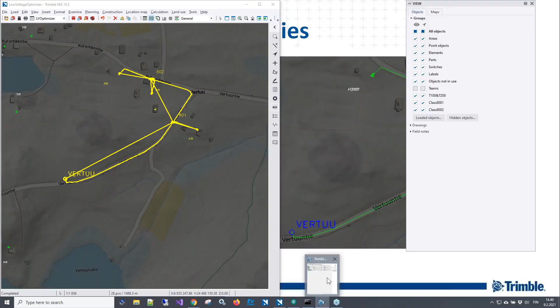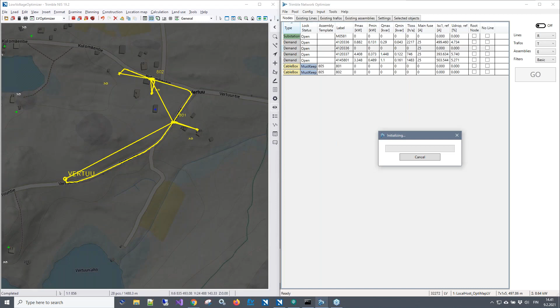So I choose the network: the feeding point, DCP substation, and the old customer points from the previous calculation. In addition, I'm choosing the lines I want to include, and the new customer point I want to investigate, to find which of the cable boxes in the existing network would be the ideal location for feeding this 25 amp new connection point.